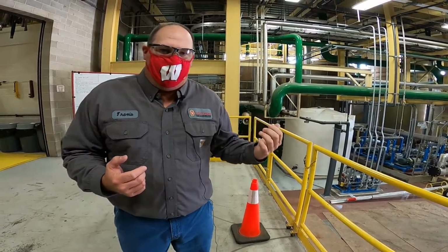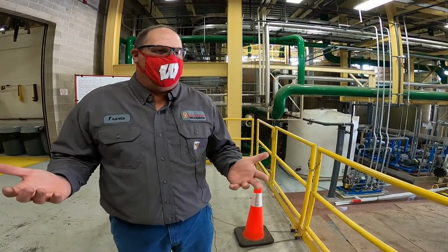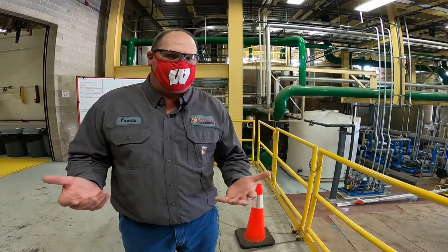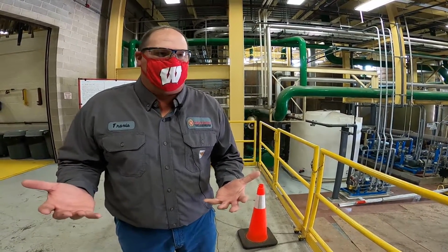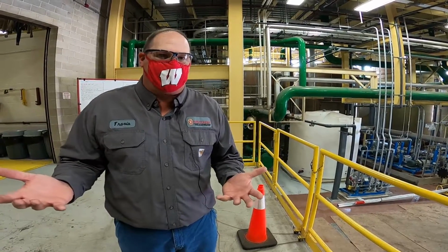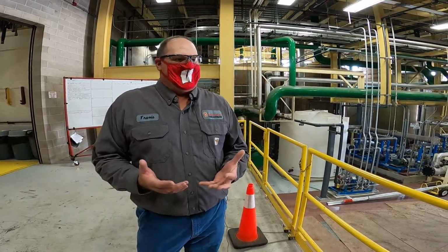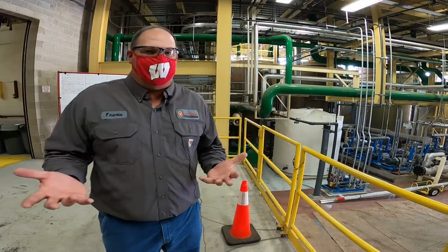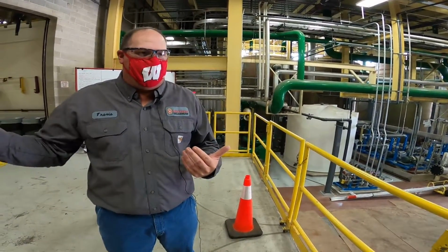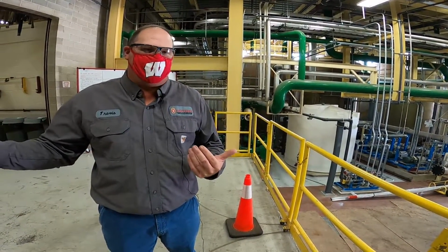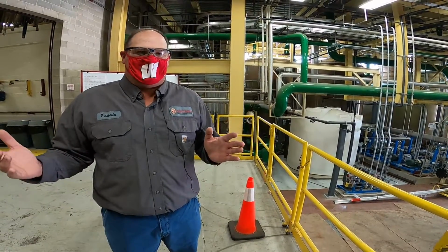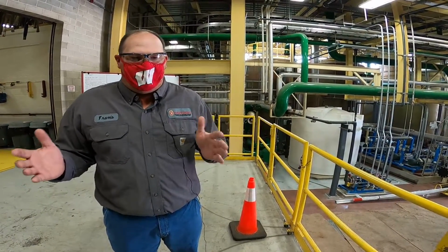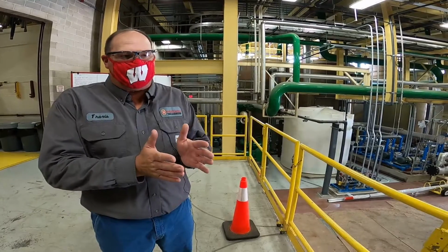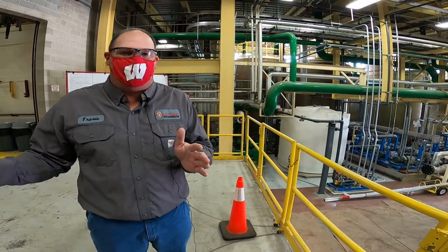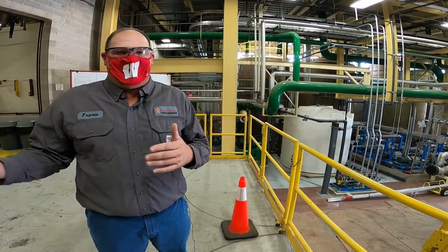Water coming from the lake is lake temperature, which can be anywhere from 38 degrees all the way up to 75, maybe 78 degrees in the summer. City water is 55 degrees. Condensate coming back is about 170 degrees. So there's a lot more BTUs that go into the water that's, say, 70 degrees versus 170 degrees.